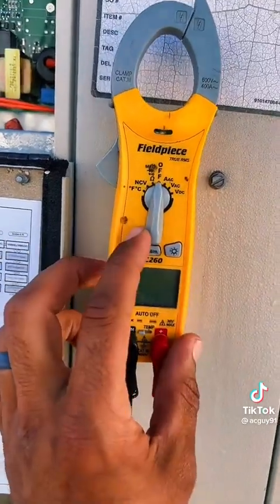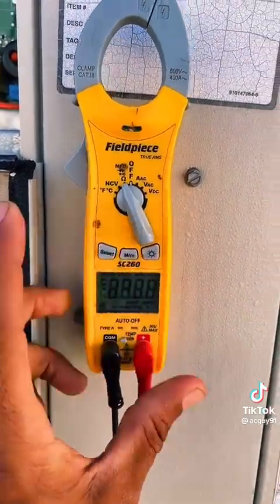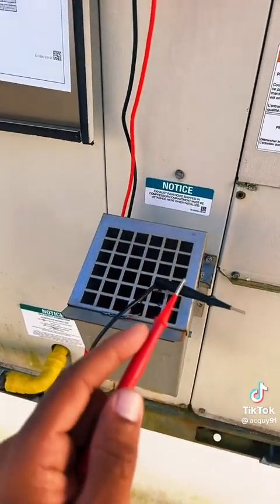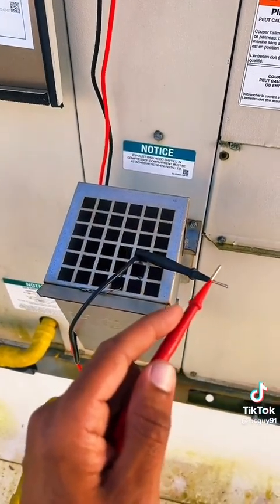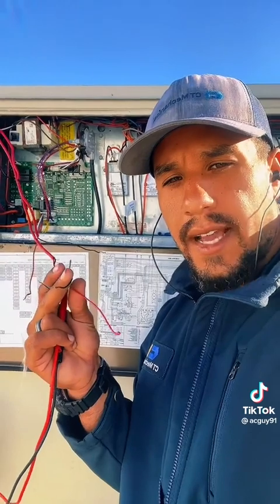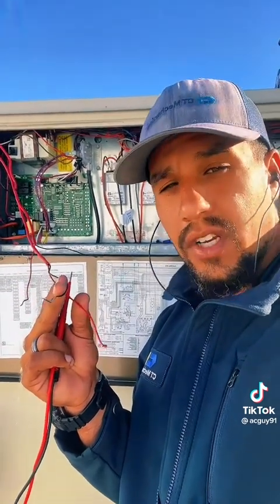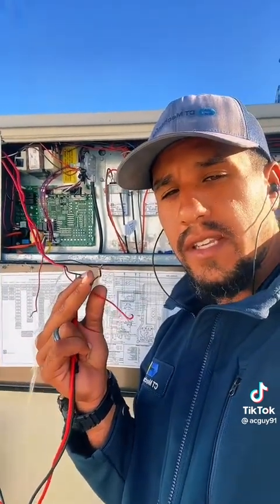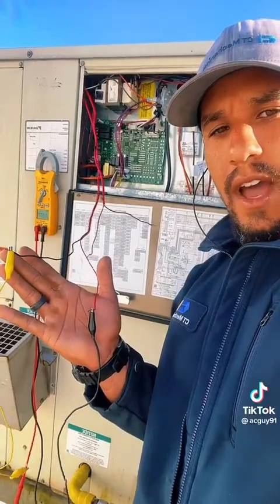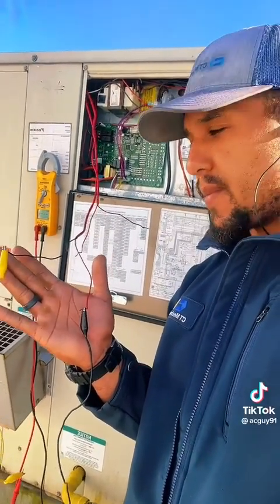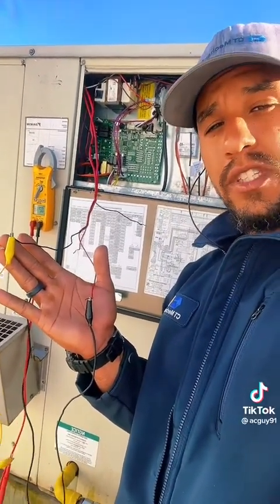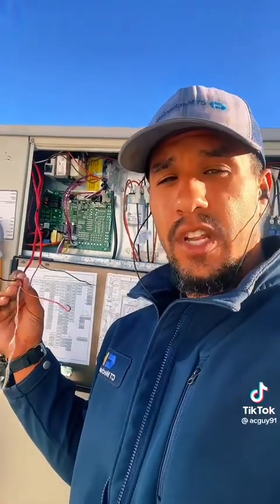So first things first, I'm gonna put my meter in continuity. Then I'm gonna make sure everything's working like it's supposed to. All right. Contact is supposed to be closed so power can go across it. When I touch each meter lead to these wires, I should hear a beep. So right now I'm connected. I have no beep. That means right now I have an open circuit. Remember, open, power can't cross. Closed, power can cross. We want closed. Right now we're open. So another way I can verify that is I'm gonna do a quick bypass.